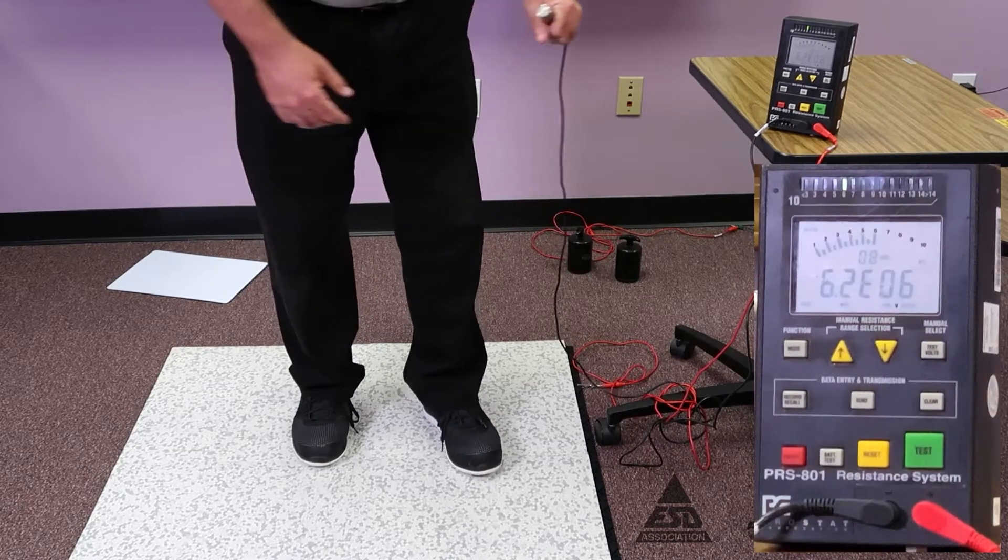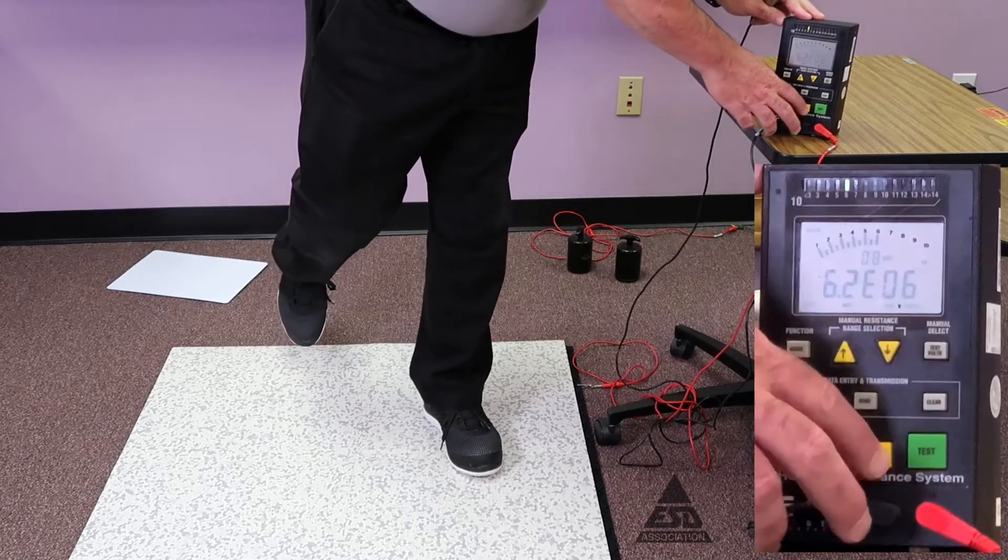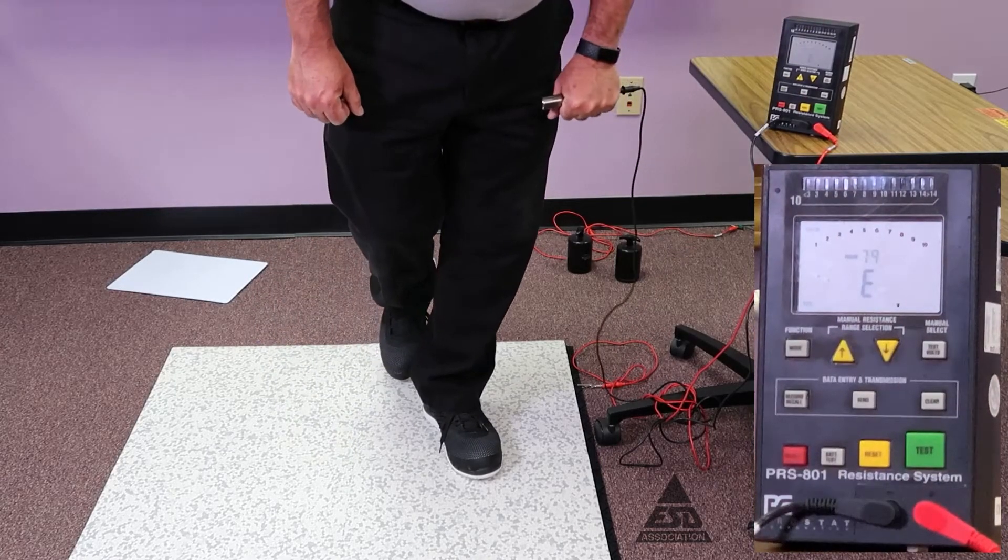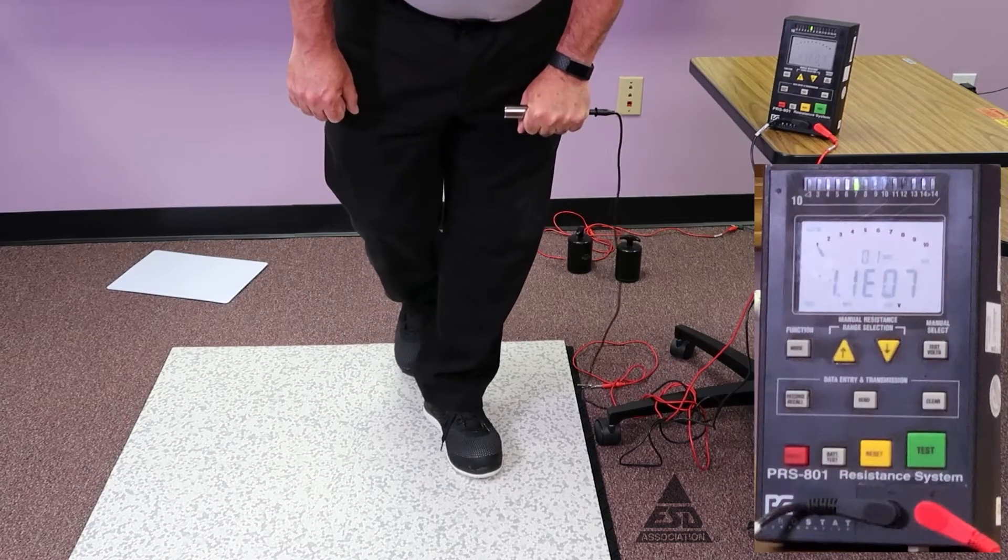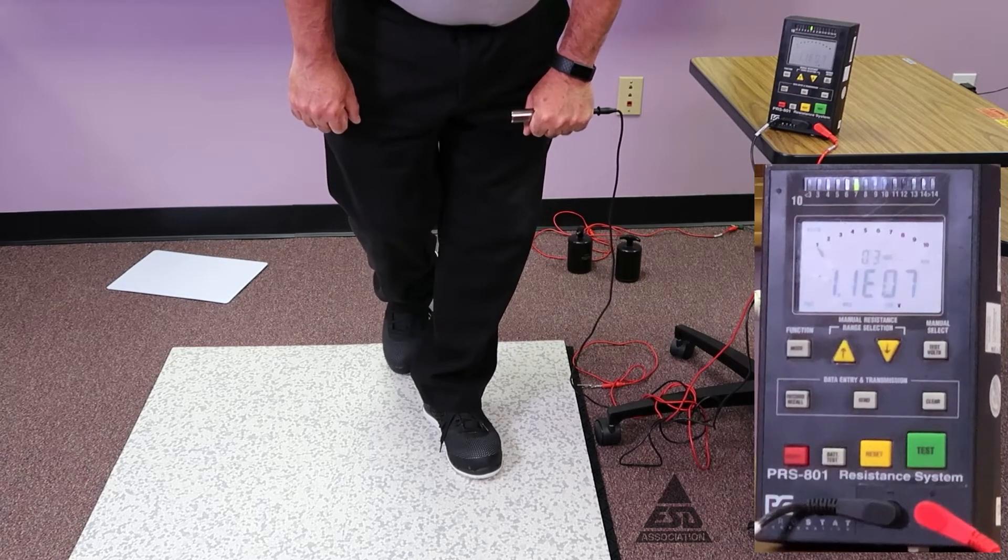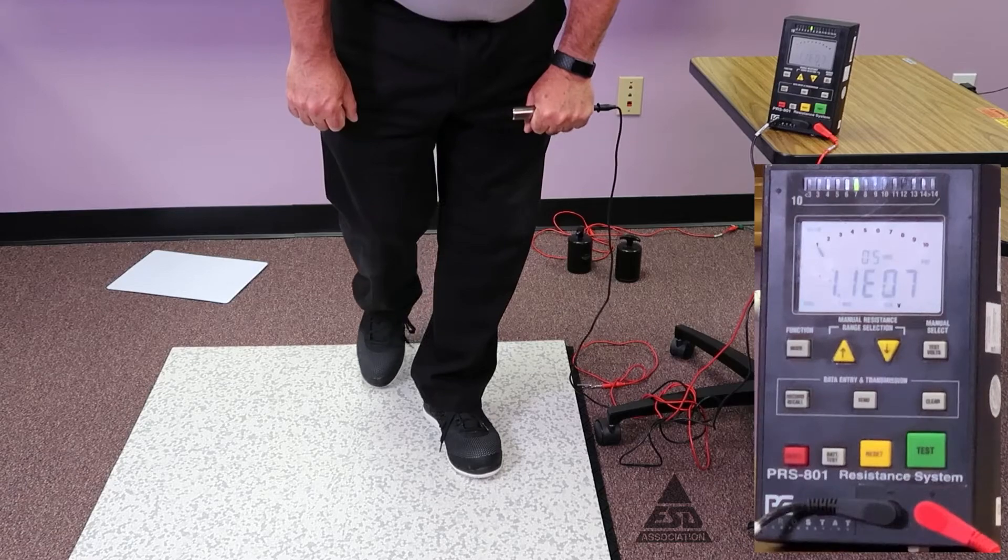Then you have to measure each foot individually. I'll do my left one first. Which is 10 to the 7th, almost 10 to the 8th, still within spec.